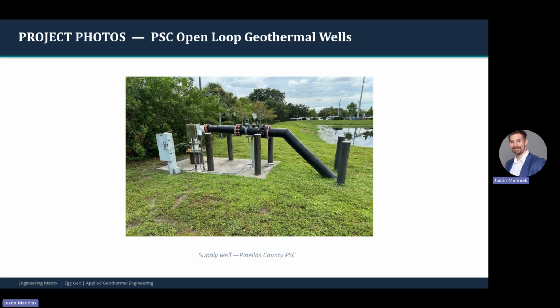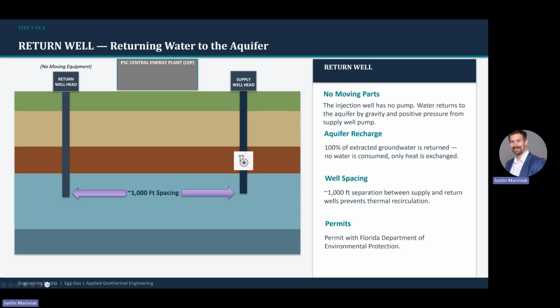Here's a photo of a supply wellhead. You'll notice that there is an electrical disconnect for the submersible pump. The next component is the return well. These are constructed similarly to supply wells. However, they do not have a pump. 100% of the water pumped out of the supply well is returned to the aquifer, a few degrees warmer. These particular wells are spaced more than 1,000 feet from one another. Distance helps to prevent short-circuiting of the water. These wells are permitted by the Florida Department of Environmental Protection.